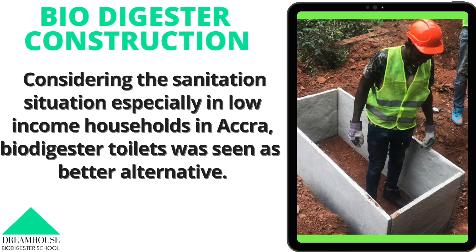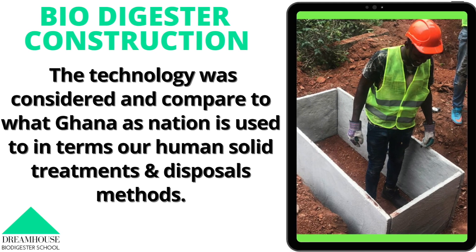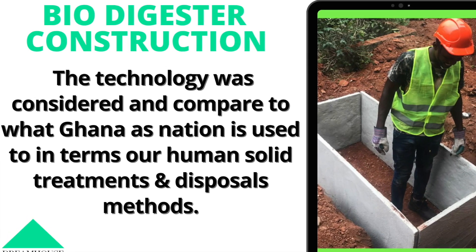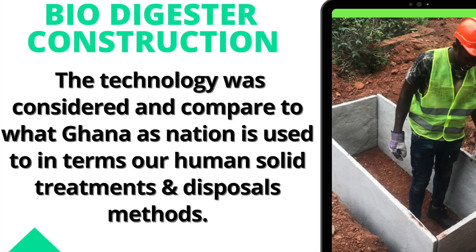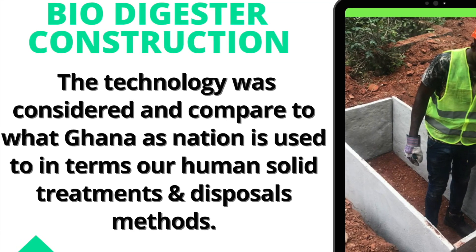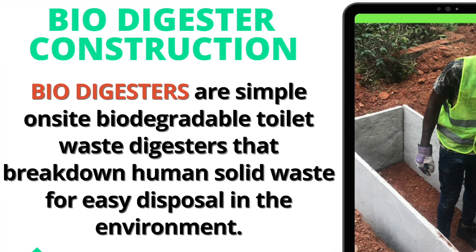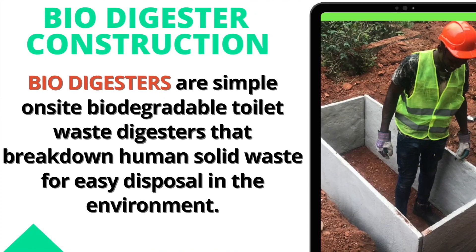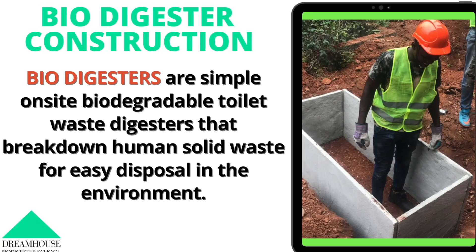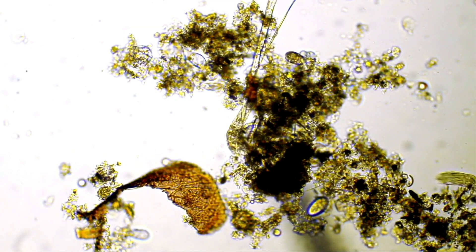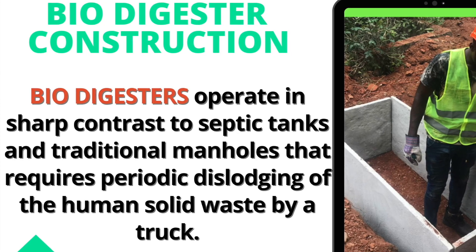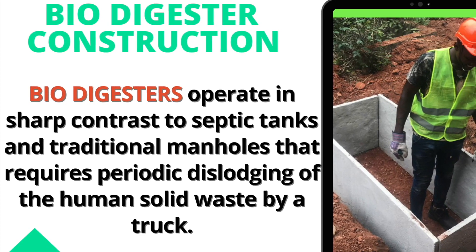There are various forms of biodigesters, but what we are going to learn in this course is the bio-fill type that has been designed, implemented, and has governmental approval in Ghana. I will teach you the two main forms — the one that started biodigester construction in Ghana and the new improved one with enhancements. A biodigester is a simple on-site biodegradable toilet wastewater technology that biodegrades human waste and treats fecal matter through a process known as anaerobic digestion, where naturally occurring microorganisms break down human waste in the absence of oxygen, so the effluent produced is clear, odorless, and fly-free, and can be safely disposed of in the environment.